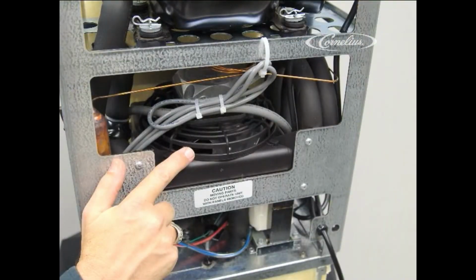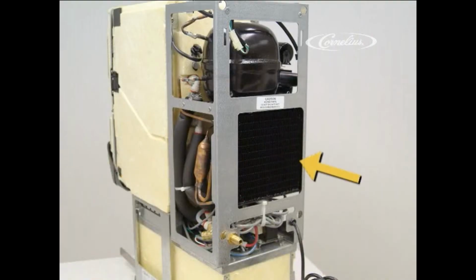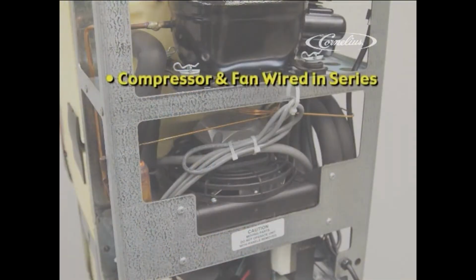The condenser and fan assembly is located here in the back of the unit. The Quest 4, as you can see, is mounted horizontally while the condenser on the Quest 2 is vertical. The condenser fan is wired in series with the compressor itself. When the IBC calls for cooling, a relay closes, sending line voltage to both this fan and the compressor.